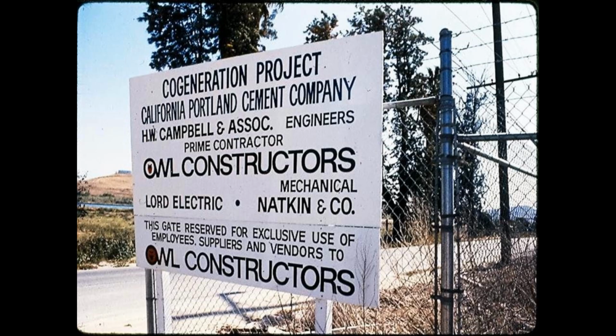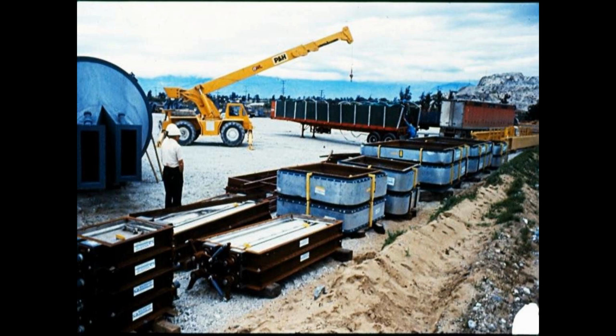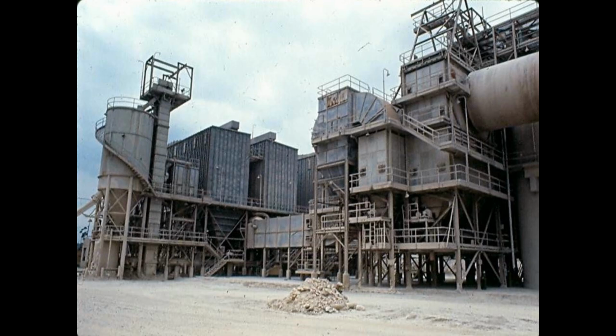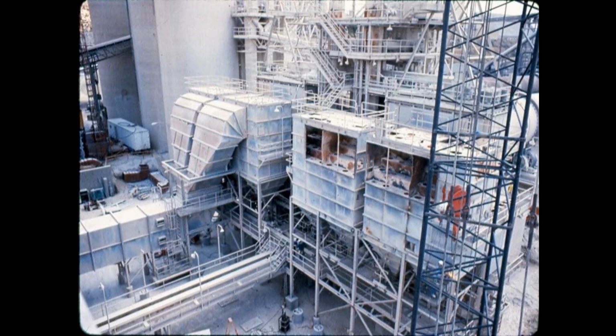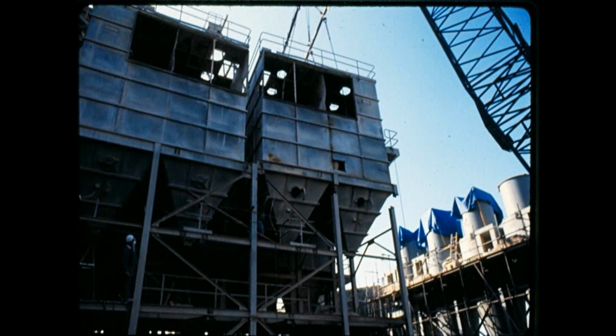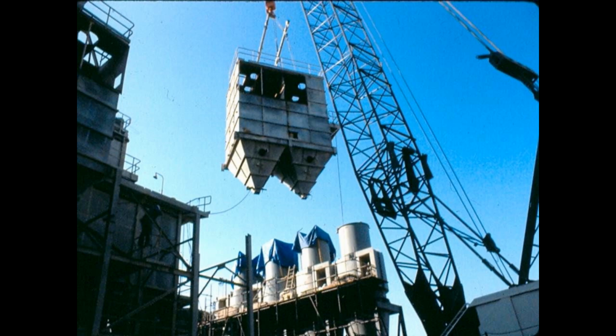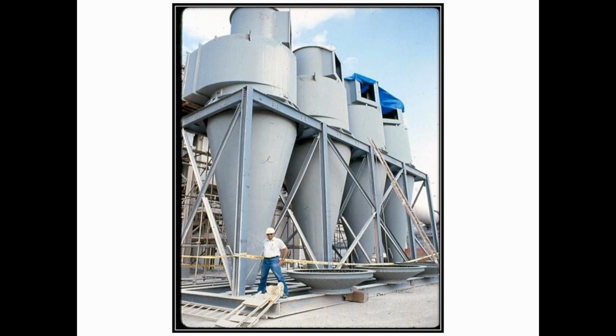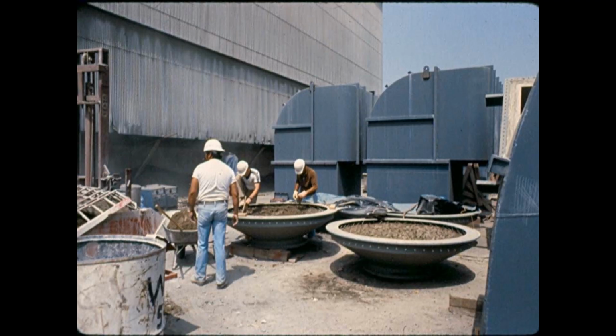In 1982, construction was begun on the project, and contractors all moved on site and began the installation process. Gases which discharge from the rotary cement kilns are contaminated with a significant amount of fine particulate matter which becomes entrained in the gases. The plant utilizes a baghouse to remove this dust so the emissions would comply with federal, state, and local air quality regulations. Prior to the addition of waste heat recovery, a significant amount of cooling air was added at the kiln end housing to reduce the temperature of the hot gases to approximately 400 degrees Fahrenheit. This was done to increase the life of the glass bags in the baghouse.